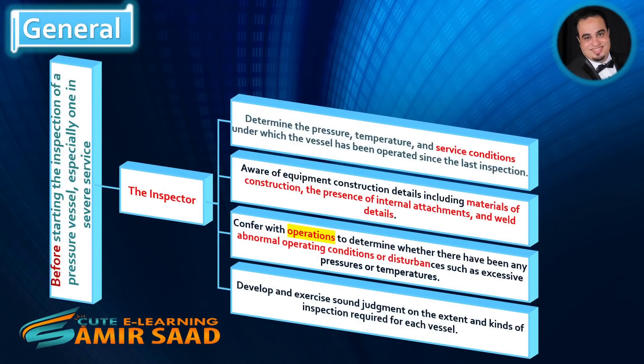Before starting the inspection of a pressure vessel, especially one in severe service, the inspector should determine the pressure, temperature, and service conditions under which the vessel has been operated since the last inspection. The inspector should also be aware of equipment construction details, including materials of construction, the presence of internal attachments, and weld details.